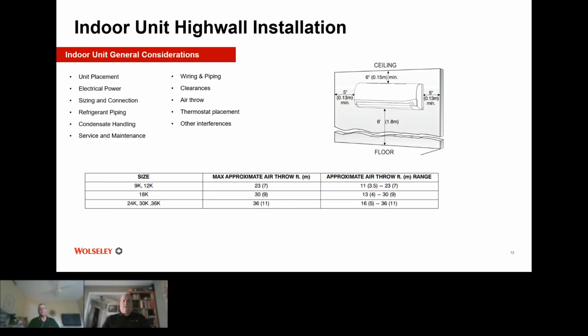Condensate handling: is it on an inside wall? Is it on an outside wall? It's much easier if it's on an outside wall, then you can just run your condensate out the back and it will drain by gravity. Otherwise, you have to put a pump in to get that water to go outside or go down in the basement into a drain somewhere.